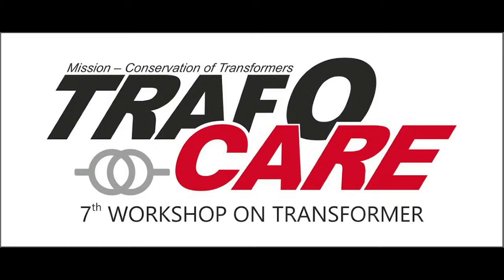My question is regarding dual winding transformers. Is the use of dual winding transformers advantageous, or should they be taken out of service? We found that for a 100 MVA, 220 by 33 kV dual winding transformer, the failure rate is higher.